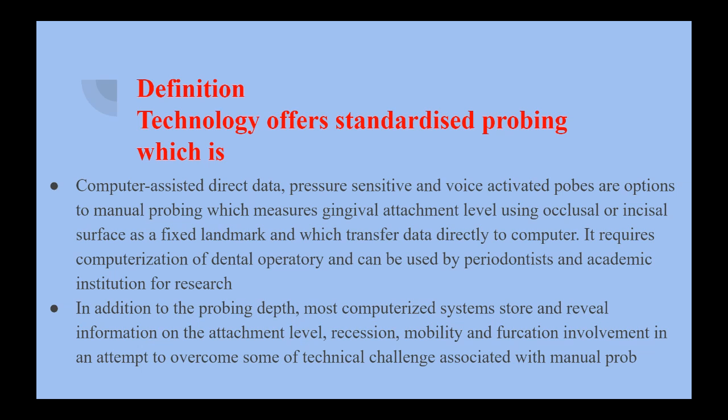What is the difference between manual and digital perio probes? The manual probes are considered first and second generation probes, and generally dental hygienists will need a second person to write down the information. Different practitioners probe at different angles and pressure, creating the possibility of differing or conflicting probing depths. It is not pressure sensitive.